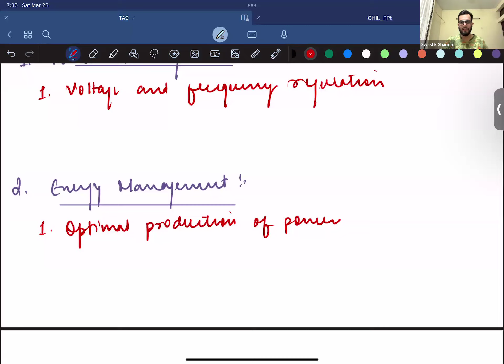Although supercapacitors can't provide power for a longer period of time, they can be used to smoothen out certain disturbances which the batteries are incapable of. Frequency regulation or smoothing are done by BESS, but the shorter transients in the system can only be supplied by supercapacitors, not BESS. You can check this yourself if you know how to read a data sheet: compare the power density of a supercapacitor versus a battery energy storage system, and you'll see which one is better able to help with a sudden transient.